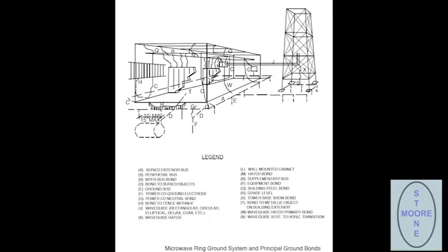That field can induce energy in all the conductors that are in that building, including this fairly sensitive electronic equipment, and so they were having problems with that. So they said, tell you what, let's isolate this equipment from building steel, any contact with building steel, and we'll take its power sources all the way back here.